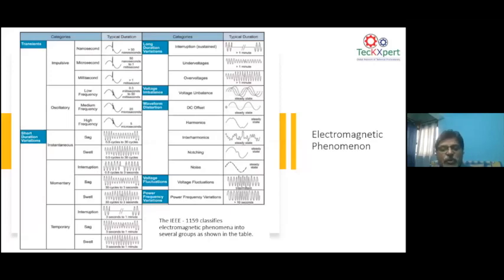And then again, another aspect is the voltage fluctuation and frequency variation. These voltage fluctuations and frequency variations are due to renewable energy sources, because when it comes to a solar or a wind farm, you can never be guaranteed voltage and frequency stability. Power output ultimately depends on the climatic conditions, the sunlight and the wind patterns. So that is why I took the initial slides to tell you that when it comes to voltage control and frequency control, if you have a varying source of voltage and frequency, then you have a problem. To control voltage and frequency, the grid operator ultimately cannot depend too much on a solar or a wind farm, because these generations are not going to sometimes contribute at the speed and response time needed. Sometimes the grid has to be stabilized.